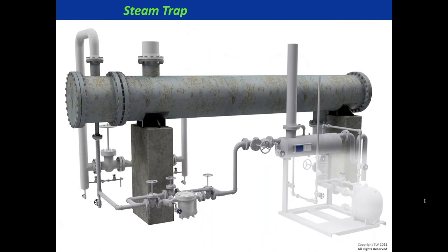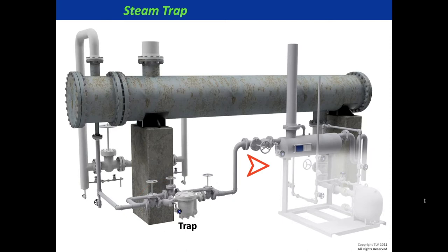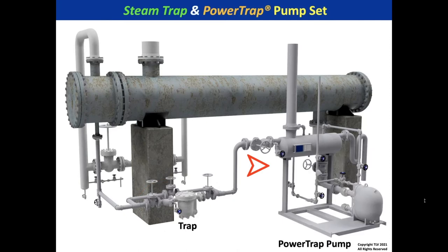For an existing installation where the trap can't go overhead, you may have enough pressure to lift condensate a few feet into a receiver. Install just a pump — not a pump trap, since you already have a trap — and deal with the flash steam using something like a vent condenser. This is one relatively easy alternative to install on existing systems.